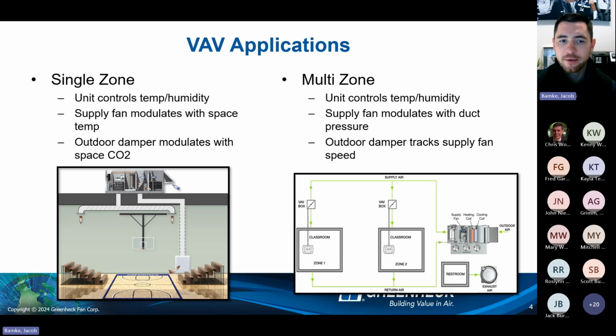And then on the flip side, you have the ventilation to worry about as well. And in most cases, this is where we start to see some demand control ventilation, where your outdoor damper and recirculation damper are going to adjust based on the space CO2.